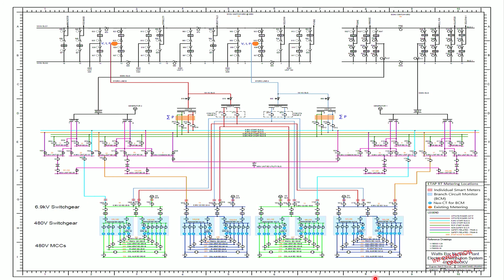Interestingly, the ETAP engineers figured out that we don't really need breaker position sensors. For all the breaker positions, so we can know the lineup of the system and what boards are connected to what sources, we can actually use the power flows, current flows, and voltage to deduce this inside the state estimator ETAP RT engine. So that was really an advantage.